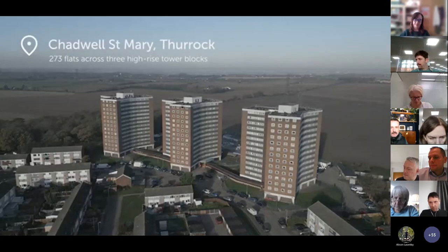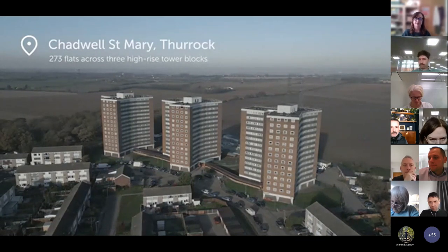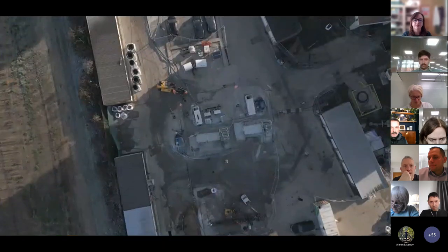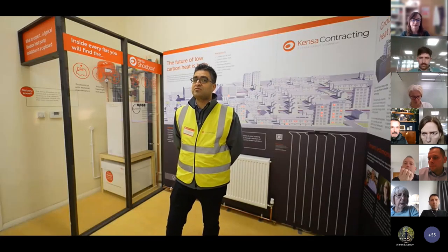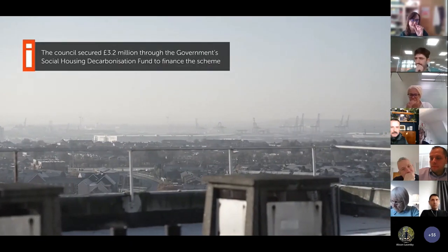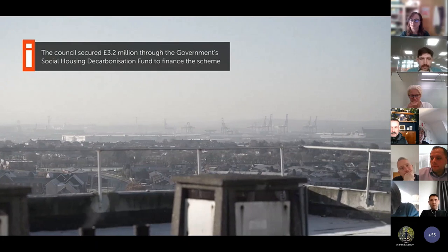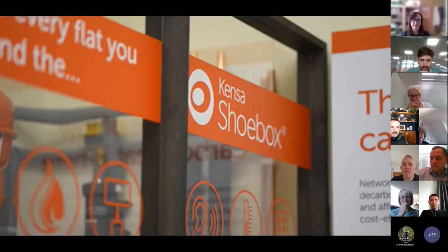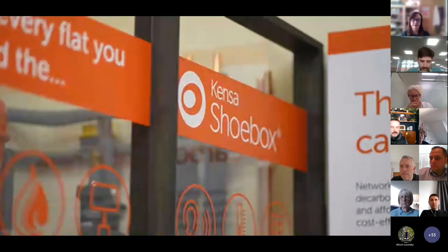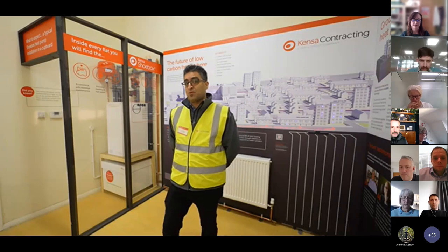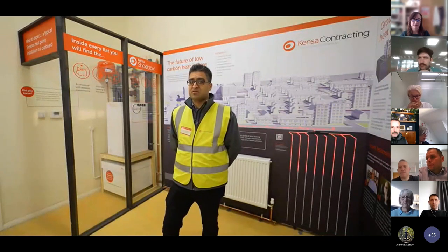Good morning, my name is Iman Barmanki and I work for Kensa Contracting. We are here today at Chadwell St Mary in Thurrock, retrofitting 3 tower blocks with ground source heat pumps connected to a shared ground array. The residents in these blocks all have electric storage heaters and are currently experiencing really high heating and hot water bills. With the energy price cap having been lifted and energy prices going up, many residents are finding themselves in fuel poverty. We're replacing those storage heaters with ground source heat pumps connected to a shared ground array. This system is much more efficient, quiet in operation, and often we see a 50% or more saving in heating bills and a 70% reduction in carbon emissions.